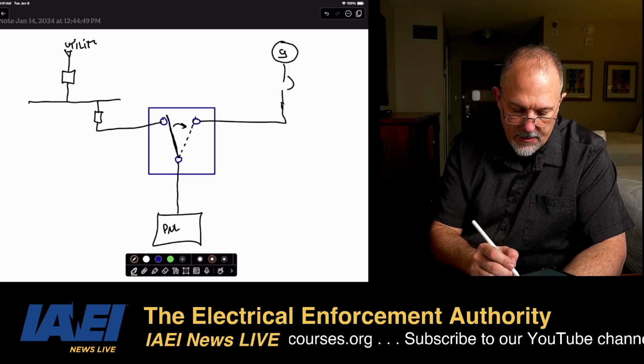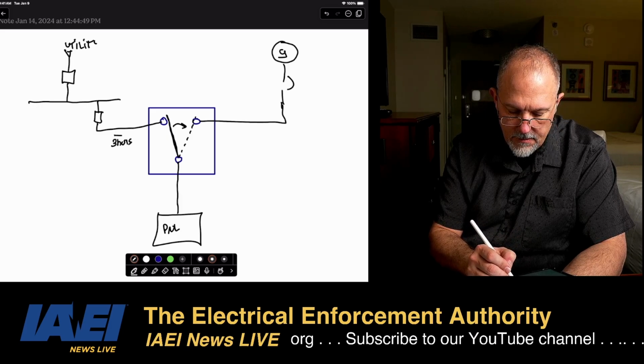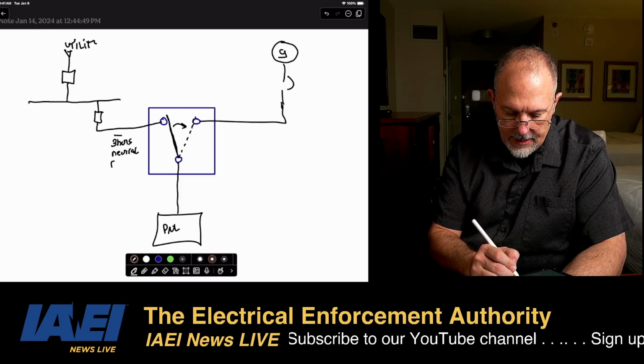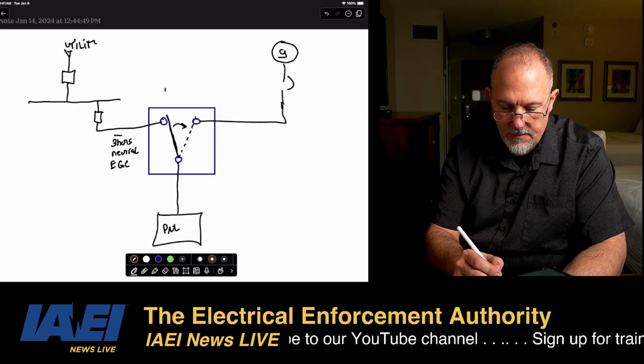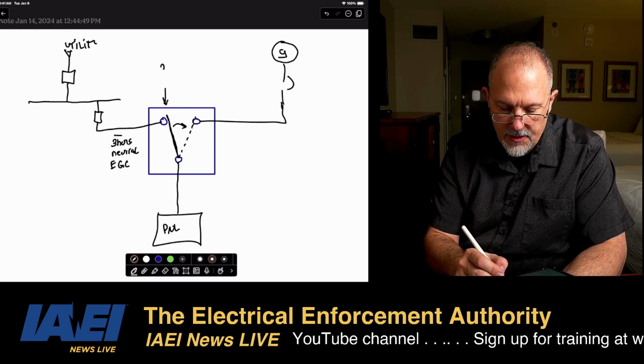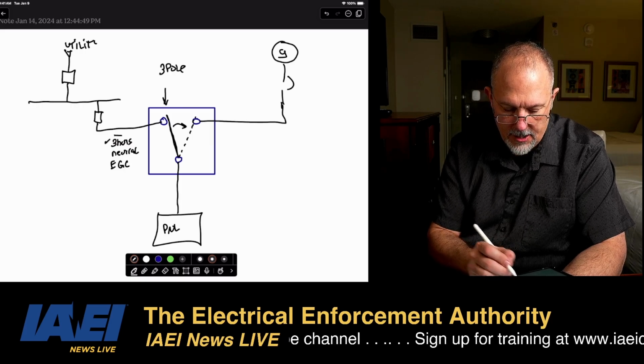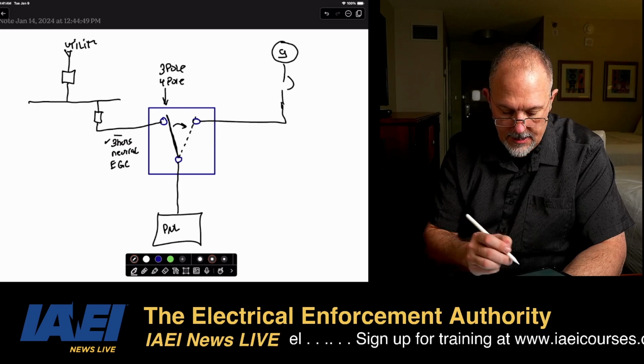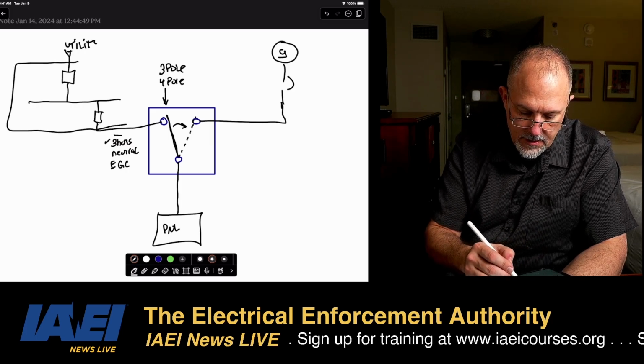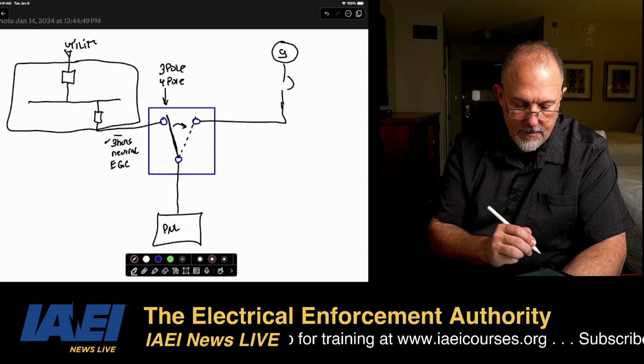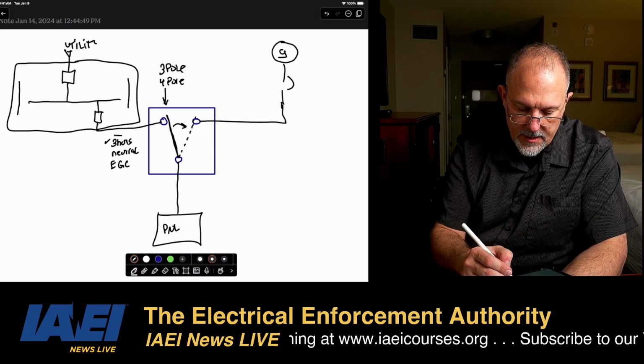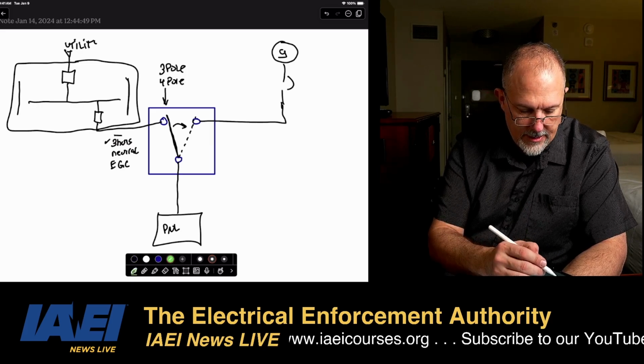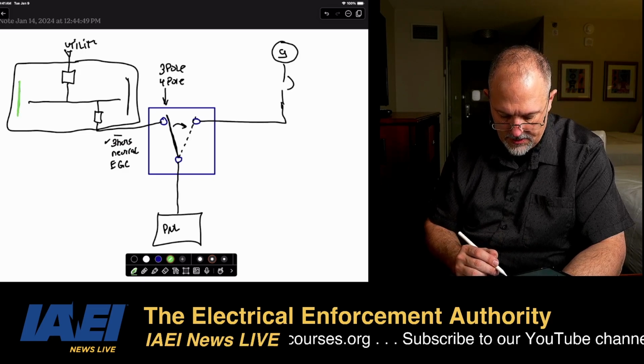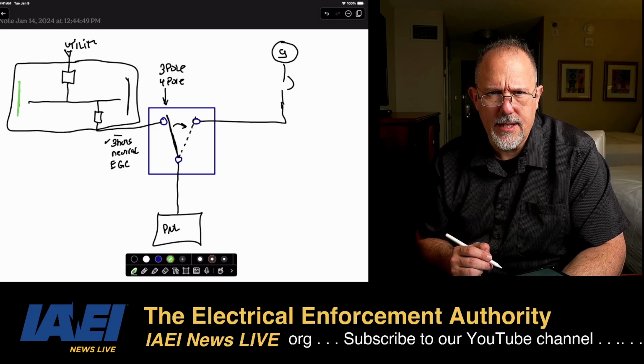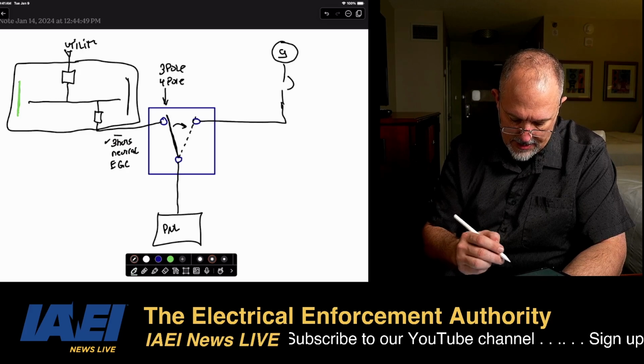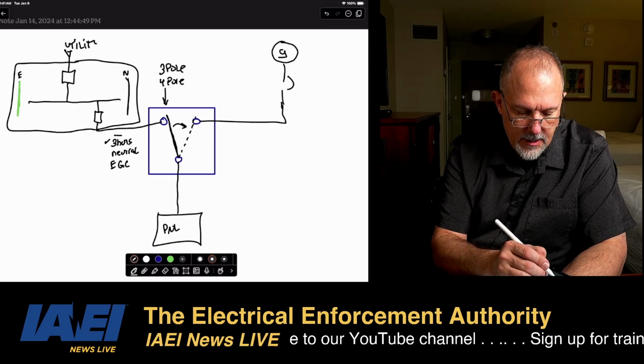Now, I have coming off of here 3 hots and a neutral and an EGC. Now this transfer switch can be a 3-pole, taking out the 3 hots, or it can be a 4-pole. Also in this equipment, I have a neutral bus and an equipment grounding bus, and I can't draw a white on white, can I? So we'll just say this is my neutral and this is my equipment grounding.